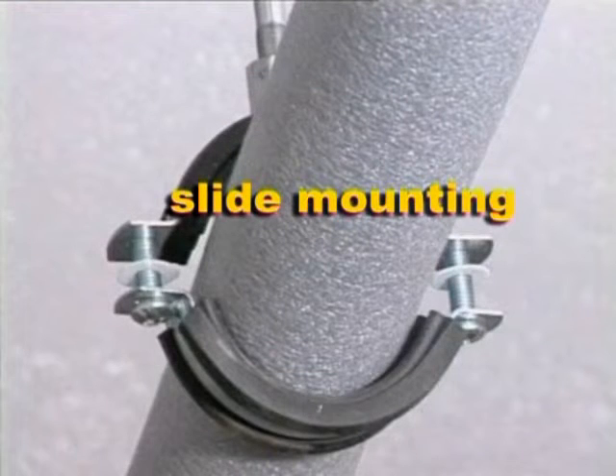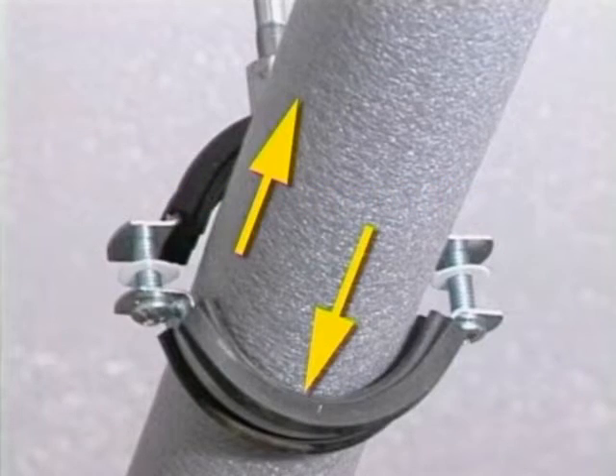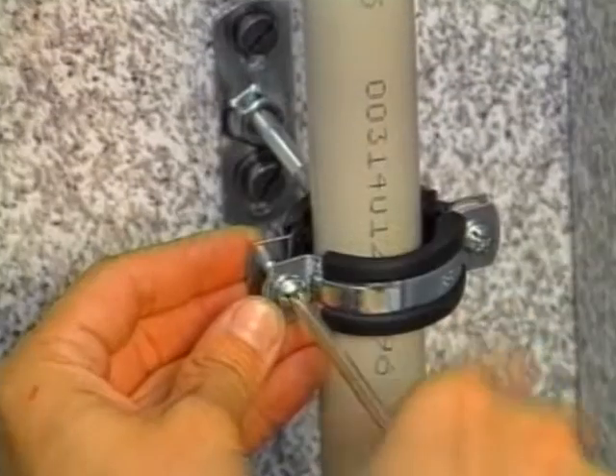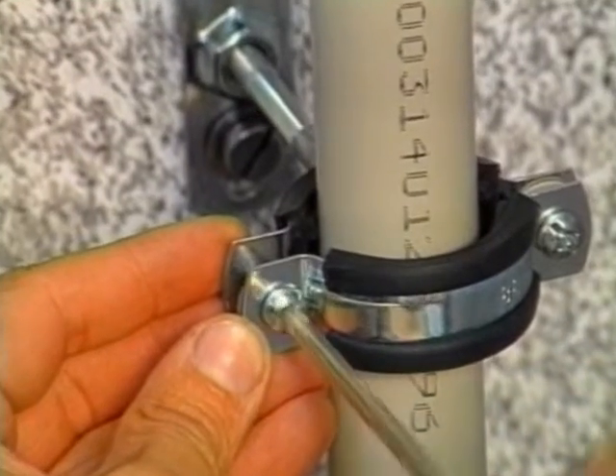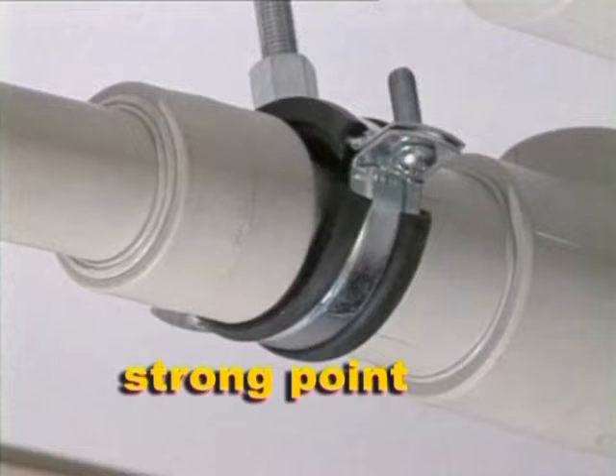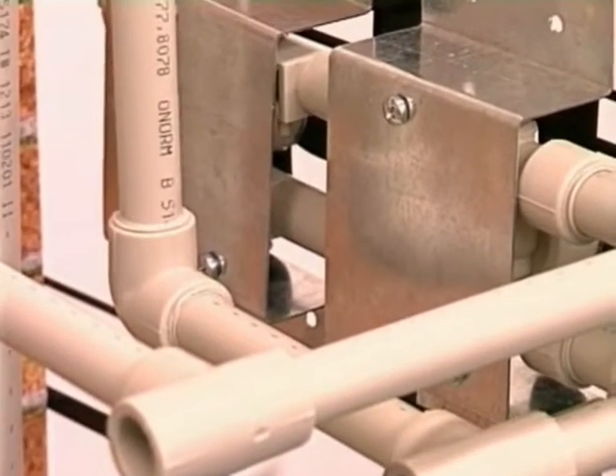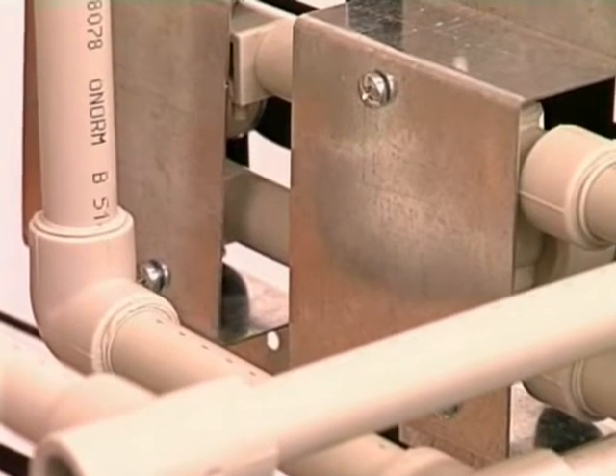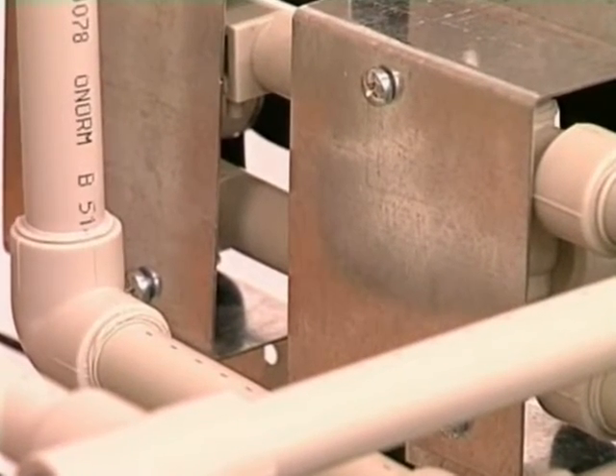A typical example is a bracket in a plastic sleeve in an insulated metal sleeve in a loose trough or on a bracket. With regard to the change in length, in some places, instead of a sliding holder, a fixed point is used. For example, a fixed point may be anchored using 2 shaped pieces and a sleeve. A fixed point may also be created in a place where there is movement of the pipe, at bends or at a water meter or fitting. We must not forget, though, that there must always be some allowance for expansion between fixed points.